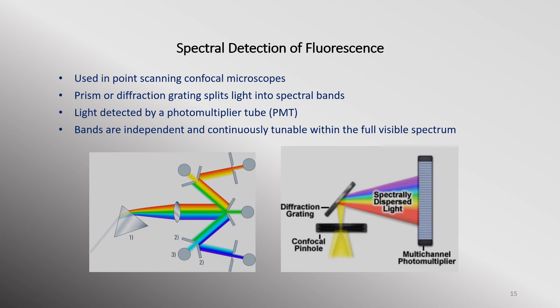Some fluorescence microscopes, in particular confocal microscopes, use prisms or diffraction gratings instead of optical filters. In this setup, fluorescence emitted by a sample is spectrally separated or dispersed spatially into a spectrum, and then split up into a series of spectral bands that are directed to one or more detectors. Spectral band and detector settings allow each fluorescence channel to be fine-tuned individually, ensuring the best signal-to-noise ratio for all fluorescence channels, and permits illumination at the lowest intensity possible.